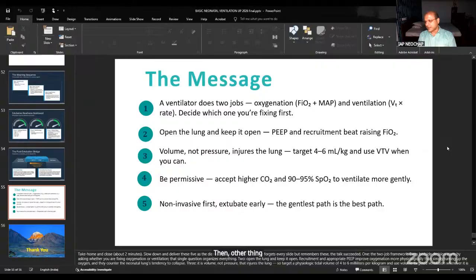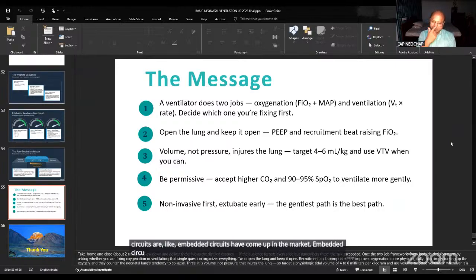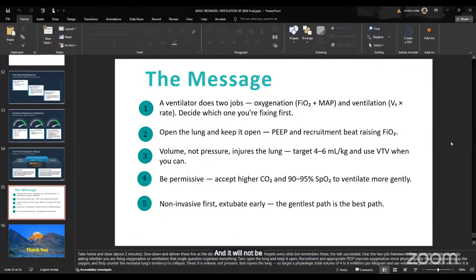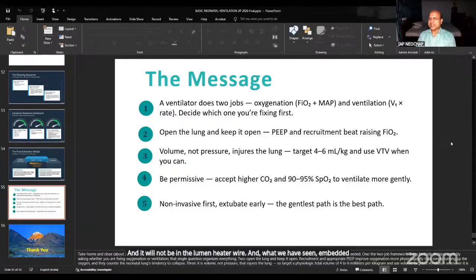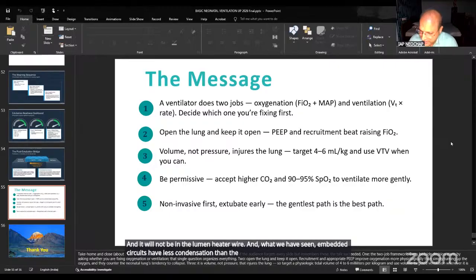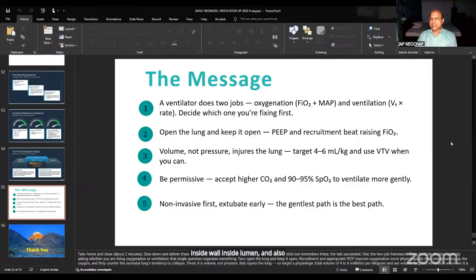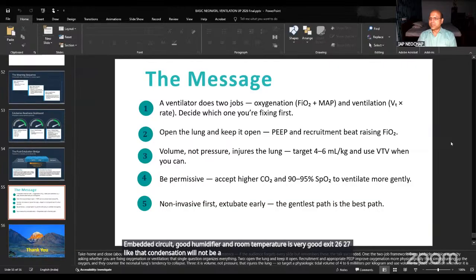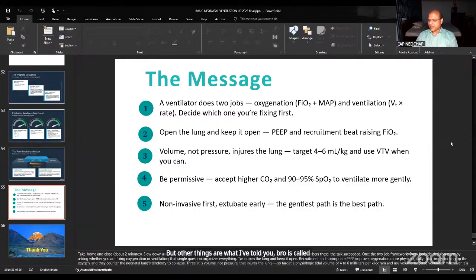Then other thing is nowadays embedded circuits have come up in the market. Embedded circuit means your heater wire will be in the wall and not in the lumen. What we have seen is that embedded circuits have less condensation than heater wires inside the lumen. Also, if we have a dual heated circuit, meaning the expiratory limb is also being heated, there also the condensation is very less. So if you have a dual heated embedded circuit, a good humidifier, and room temperature is good, actually 26, 27, condensation will not be a problem. But if the room is cold, your humidifier is not very good, or the circuit is not good, then you compromise on the circuit, and condensation will be there.